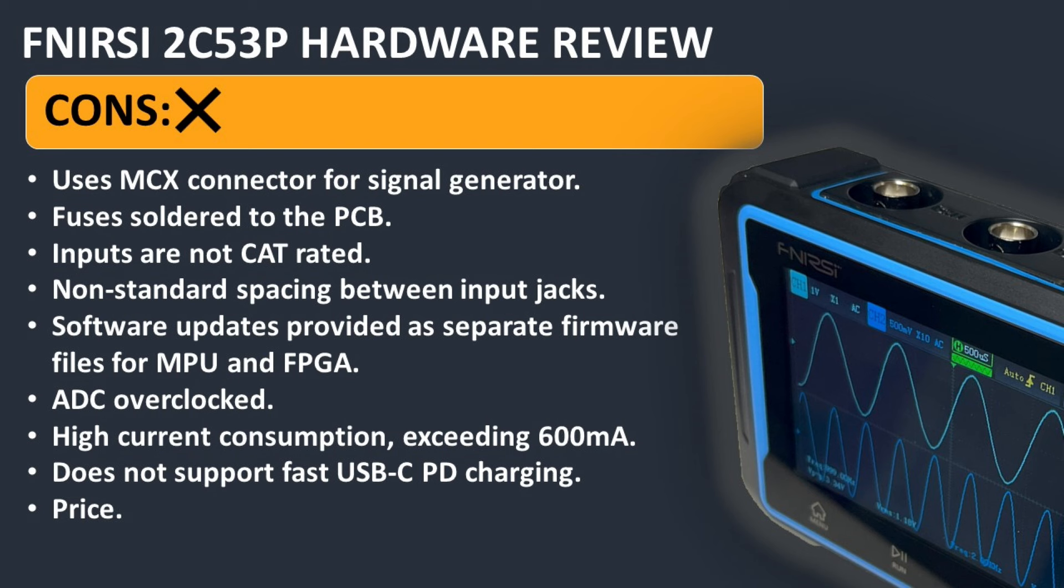Software updates provided as two separate firmware files for the MPU and FPGA. I don't like this. This is potentially risky. Normally you would have a package which would combine all your software components to reduce the risk of the two components being out of sync, i.e. one installed but not the other. I'm surprised there's not some sort of container or package to control that. It just puts more risk in the user getting their software updates wrong. So I do hope they change that. The ADC appears to be overclocked. I say it appears to be - I don't see how that could be misinterpreted from the measurements we did. But we'll take a closer look at that when we do the performance review.